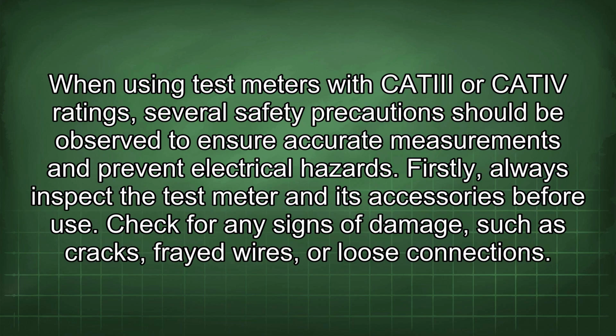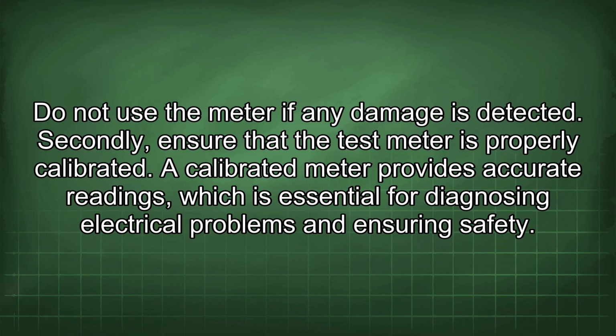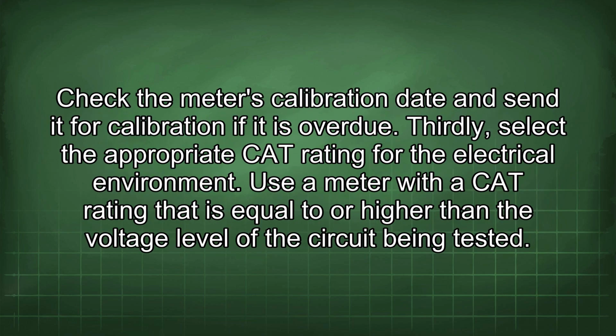When using test meters with CATIII or CATIV ratings, several safety precautions should be observed to ensure accurate measurements and prevent electrical hazards. Firstly, always inspect the test meter and its accessories before use. Check for any signs of damage, such as cracks, frayed wires, or loose connections. Do not use the meter if any damage is detected. Secondly, ensure that the test meter is properly calibrated. A calibrated meter provides accurate readings, which is essential for diagnosing electrical problems and ensuring safety. Check the meter's calibration date and send it for calibration if it is overdue.